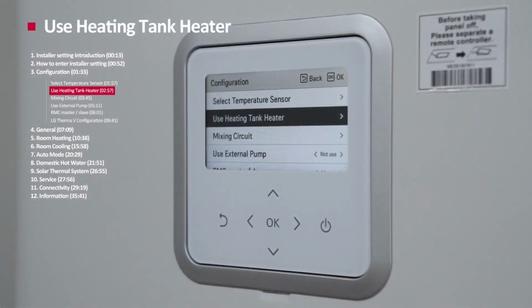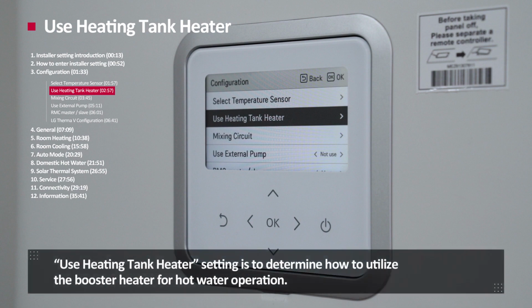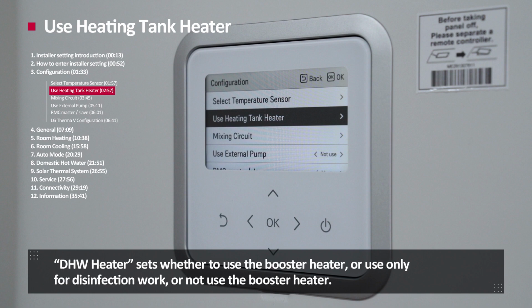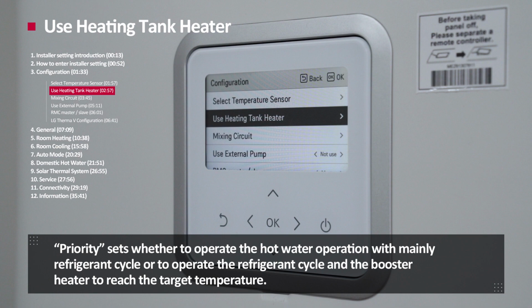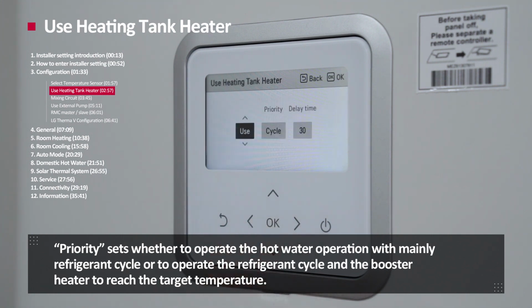Use heating tank heater. Use heating tank heater setting is to determine how to utilize the booster heater for hot water operation. The DHW heater sets whether to use the booster heater or use only for disinfection work or not use the booster heater. Priority sets whether to operate the hot water operation with mainly refrigerant cycle or to operate the refrigerant cycle and the booster heater to reach the target temperature.